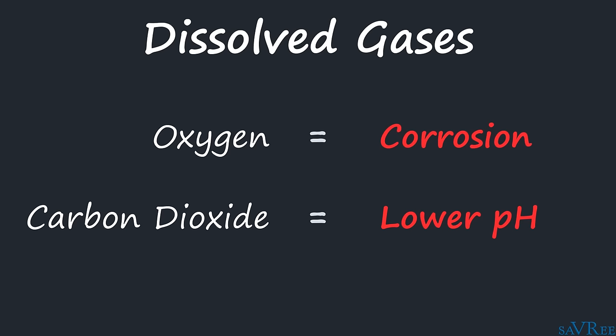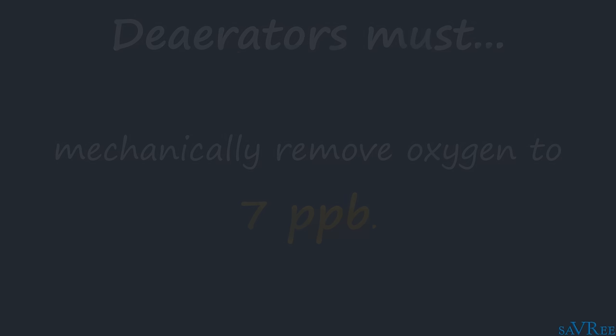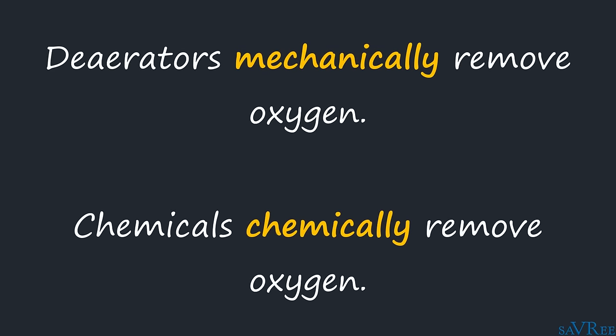In order to protect our boiler and many of the associated components including piping and valves, we need to remove as much oxygen and CO2 from the boiler feed water as possible. A typical deaerator will be designed to mechanically remove oxygen down to a level of about seven parts per billion. Any oxygen that remains after being stripped by the deaerator will be removed chemically. These oxygen scavenging chemicals are typically sodium sulfite and hydrazine.